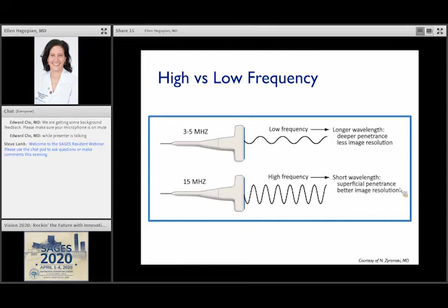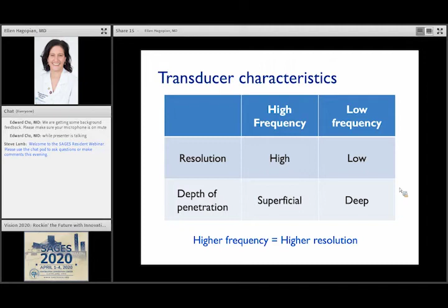This is in opposition to high frequency probes, 11, 12, up to 15 we use in the operating room. High frequency probes, short wavelengths, have superficial penetration or less penetration, but much better image resolution. And we will look at some examples of that in a little bit. So just to reiterate, resolution: high resolution, high frequency; low resolution, low frequency. The depth of penetration is superficial in high frequency and deep in low frequency.